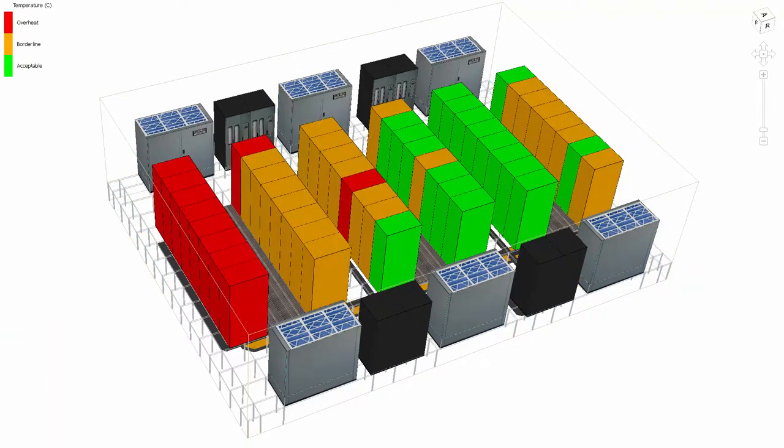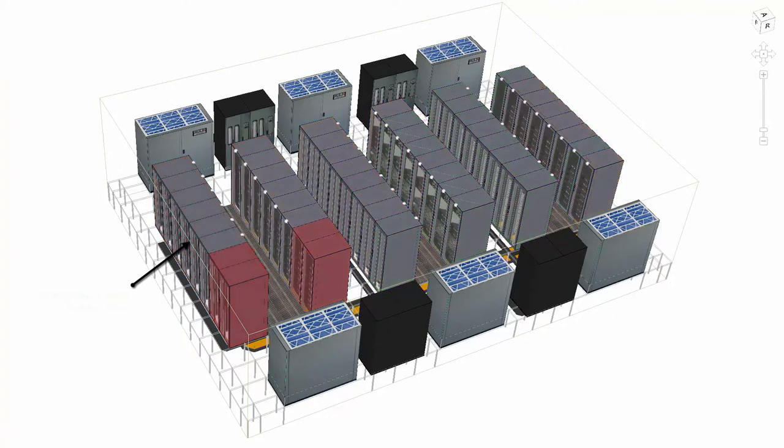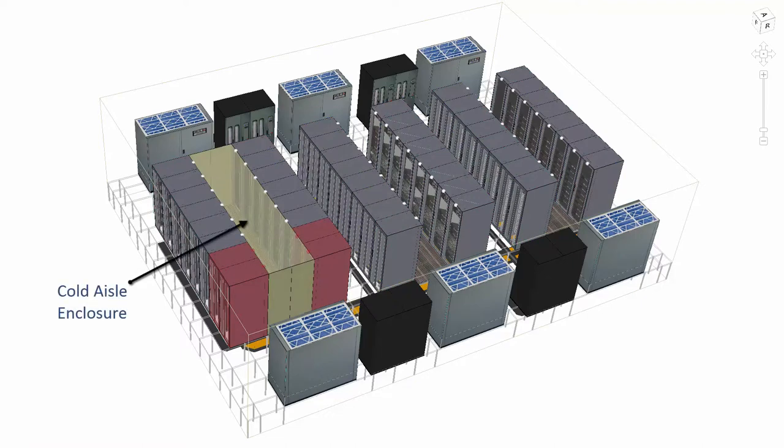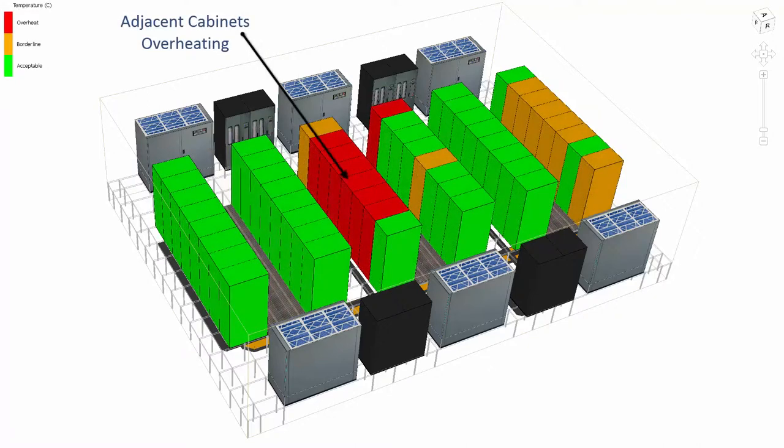In the second case, we have a hall whereby a particular row of cabinets have thermal issues. As a quick solution, the facility manager decides to implement cold aisle containment on that specific row of cabinets. Once applied, it was noticed that the thermal issues have been solved locally, but equipment in the adjacent row of cabinets were now overheating. So what has happened?